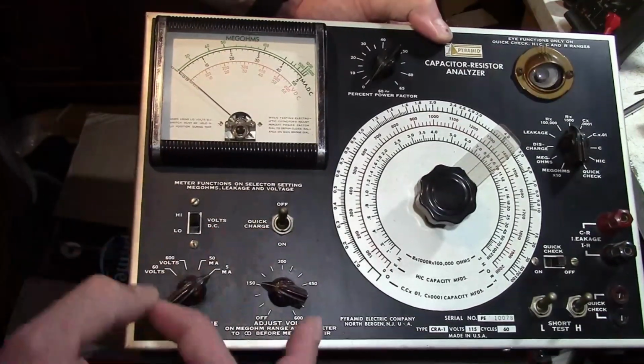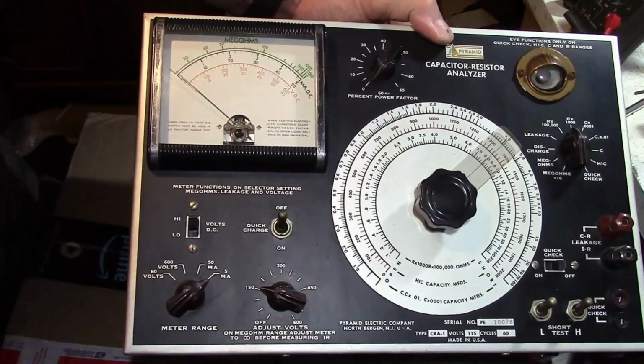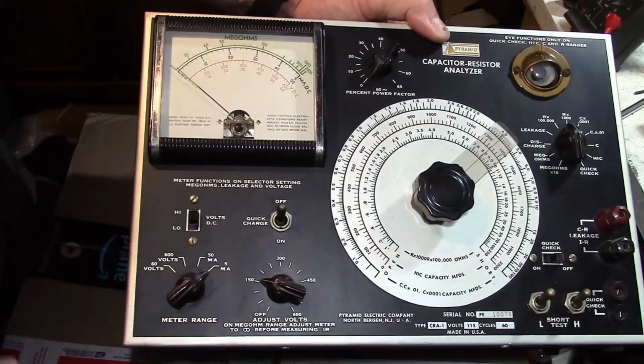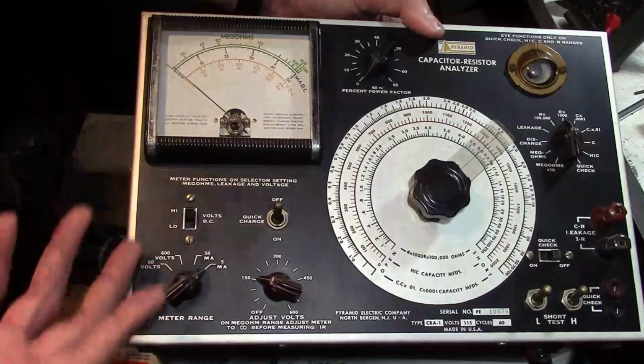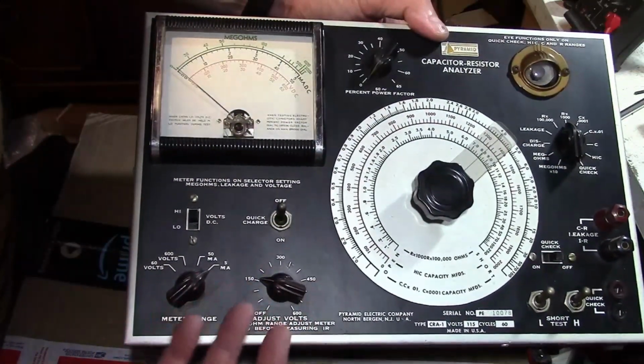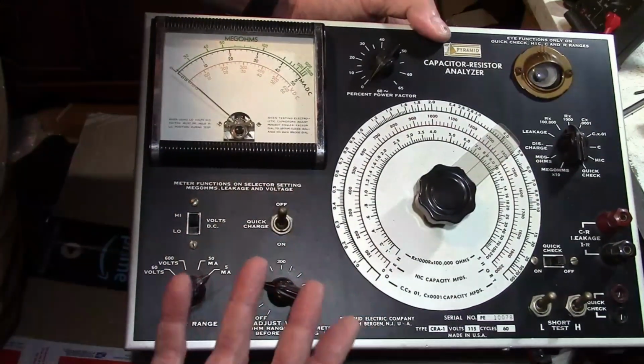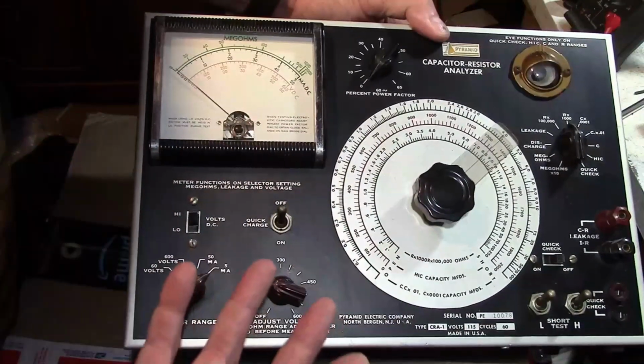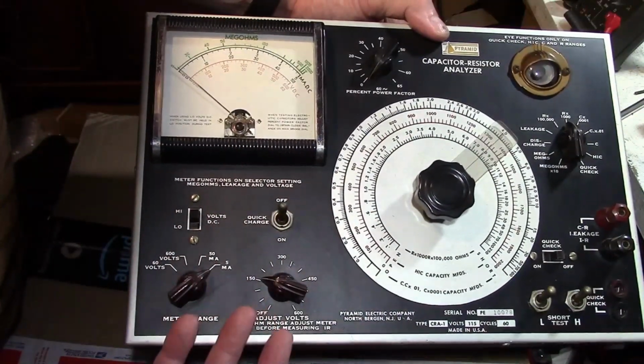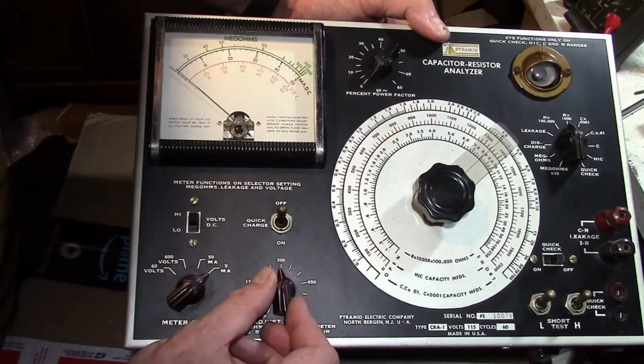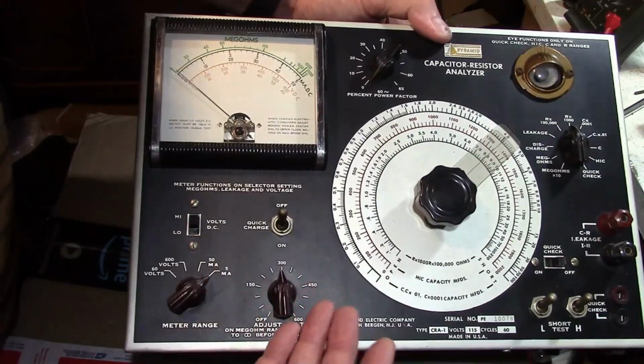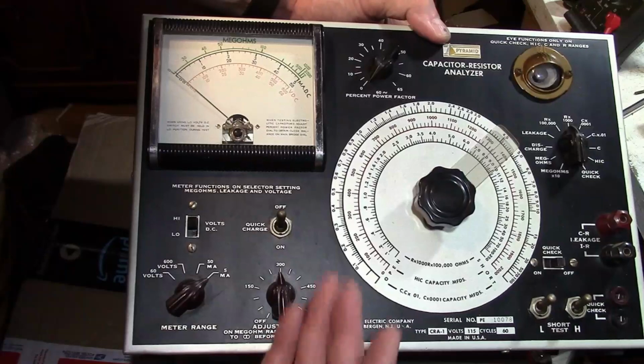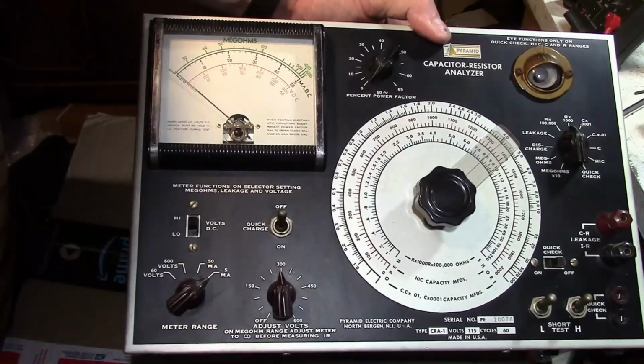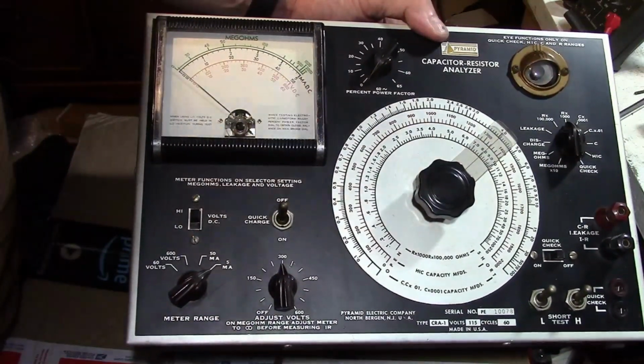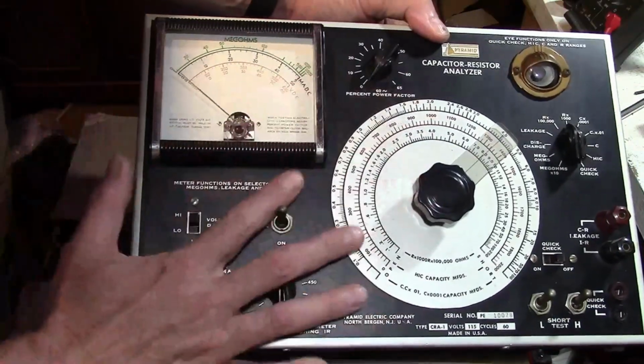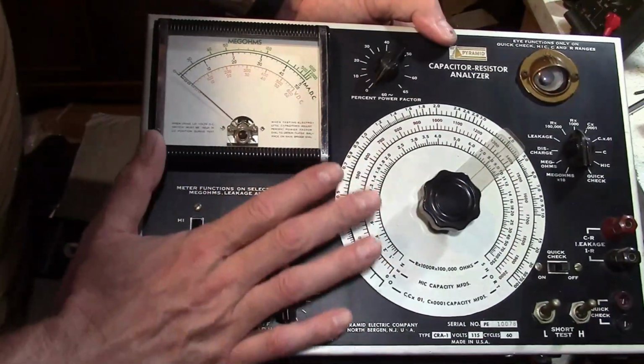I mean, ideally there'd be 0 current going through it. But when a capacitor has sat for a long time, or it's no good, you're going to have current. But by slowly applying voltage, you can reform the chemicals inside and build up an insulating layer. And ideally, you'd make it all the way up to 300 volts, or whatever the working voltage is on that cap. And the current would be down at an acceptable level, which would be, say, less than 1 milliamp. So that's the cool thing about this.